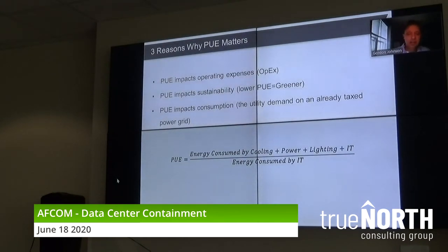PUE is defined as, in the numerator down below, you take all the energy consumed in your data center by your cooling, so the CRAC units, your CRAH units, your chilled water plant, the power in your data center, your UPSs, your generators, your lighting, and then finally you add your IT heat load in kW. And you divide that, again, by your IT heat load in kW.